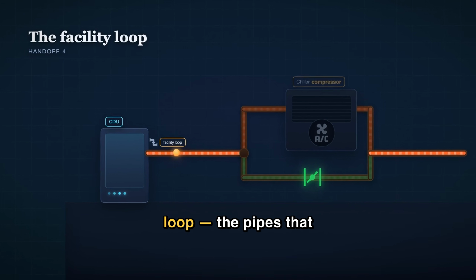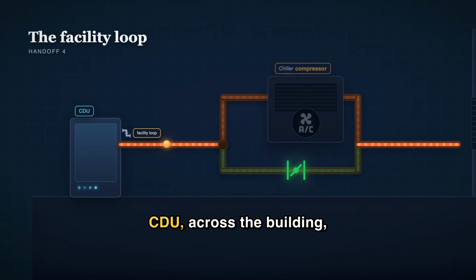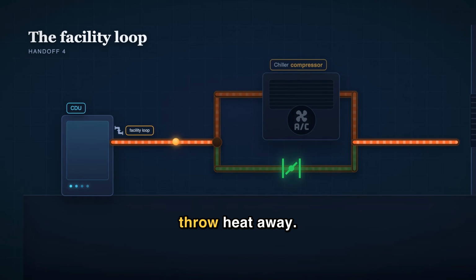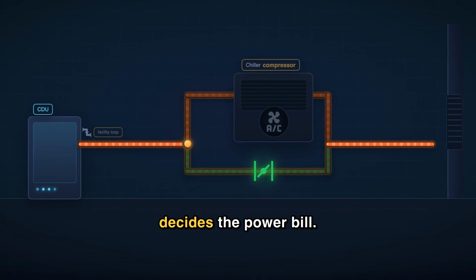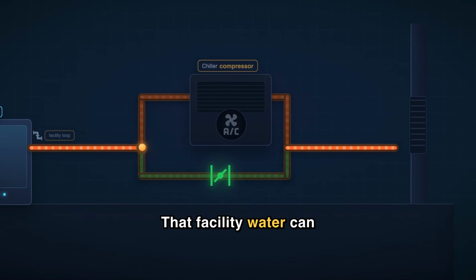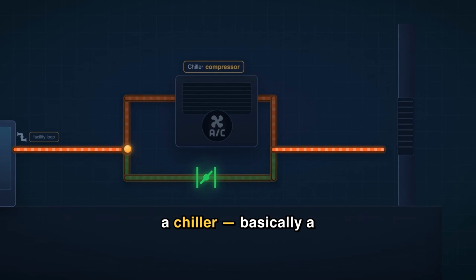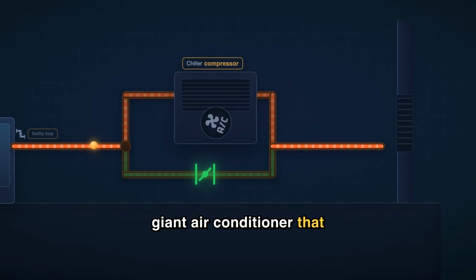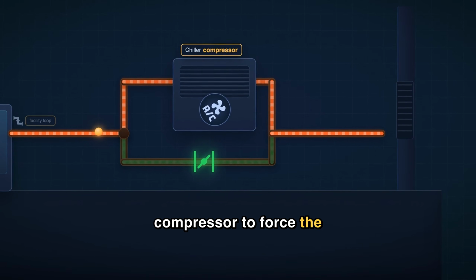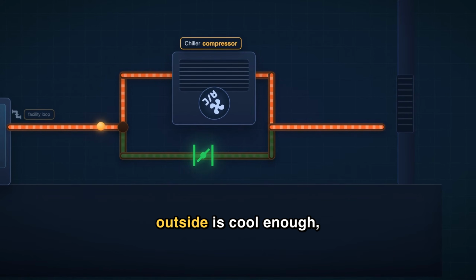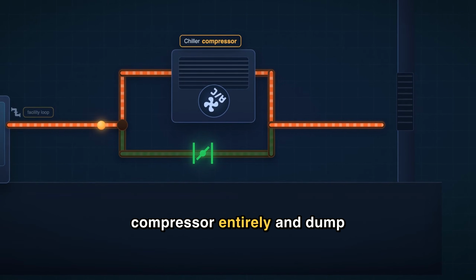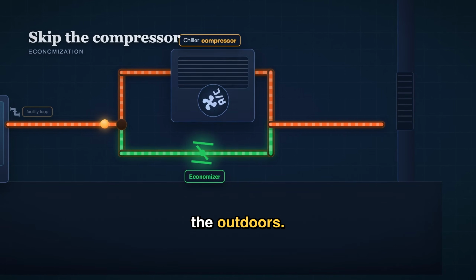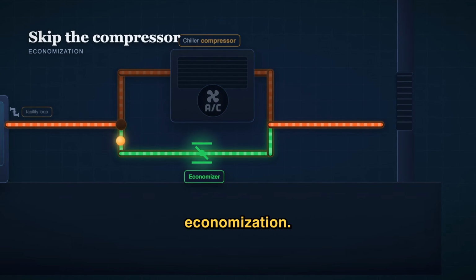This is the facility loop, the pipes that run out of the CDU across the building toward the machines that throw heat away. Here's the choice that decides the power bill. That facility water can take a detour through a chiller, basically a giant air conditioner that uses a power-hungry compressor to force the water cold. Or when the weather outside is cool enough, it can skip the compressor entirely and dump its heat straight to the outdoors. That shortcut is called economization.